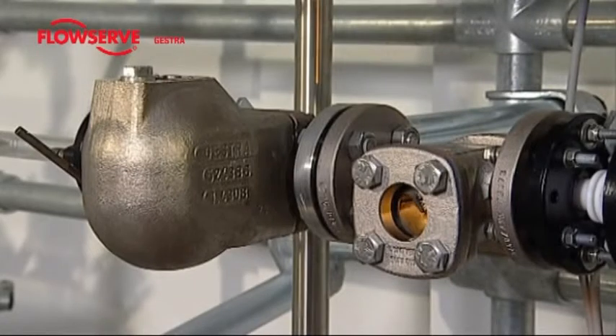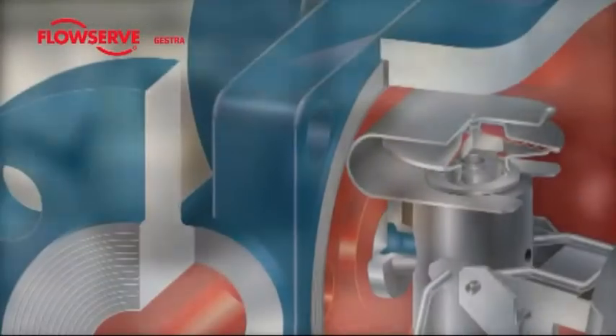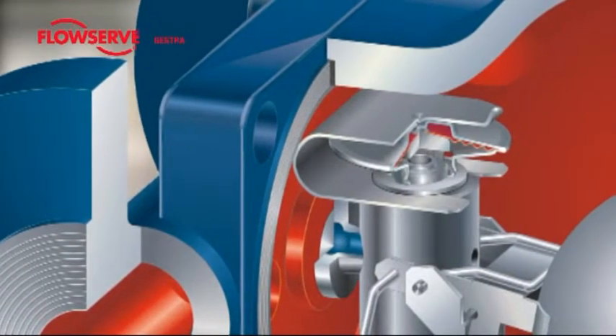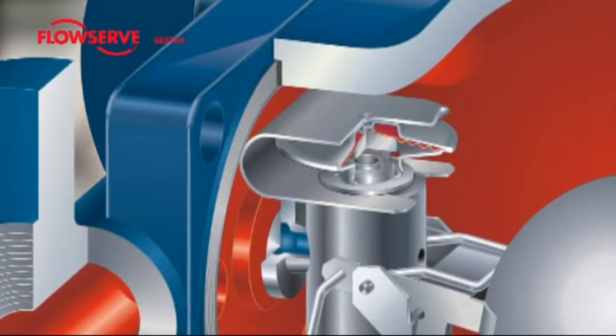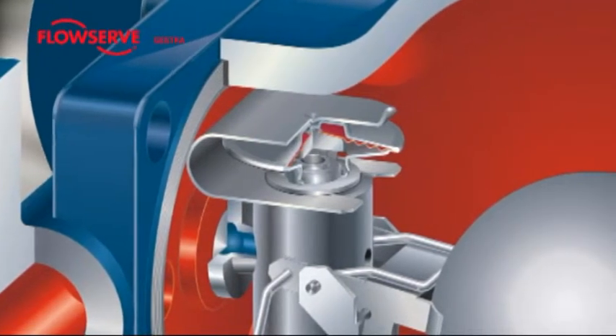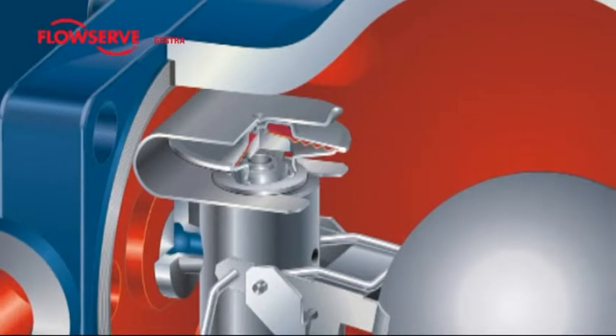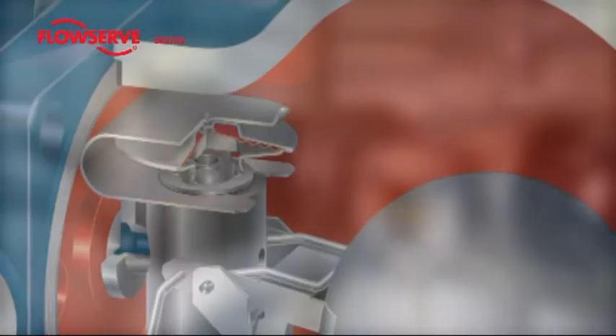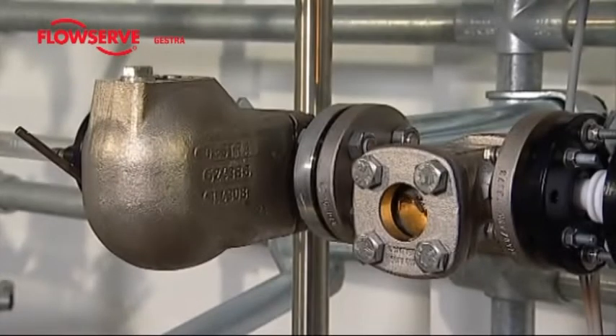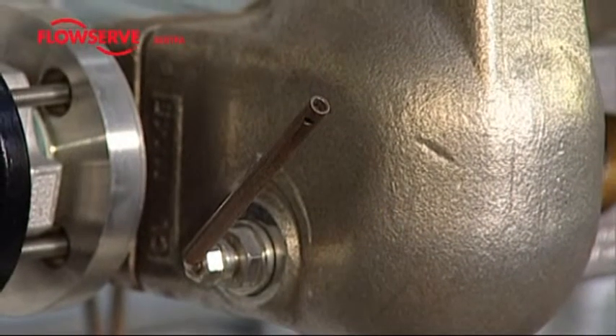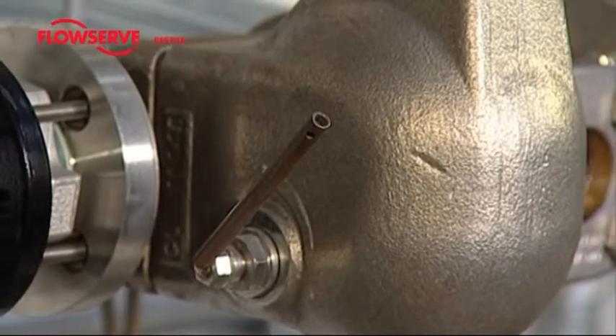At the start of every heating process, there is still air in the heat exchanger. Air or other non-condensable gases must be vented from the heating process by the steam traps, since they will greatly impair the exchange of heat. For this reason, the Gestra ball float trap has an additional thermostatic control to handle this task. With the UNA16, this is a small regulating membrane which, through the temperature difference between saturated steam and air, detects whether there are any unwanted gases in the heating system that would impair the heating process. As an optional arrangement, a float lifting lever is mounted on the float trap.